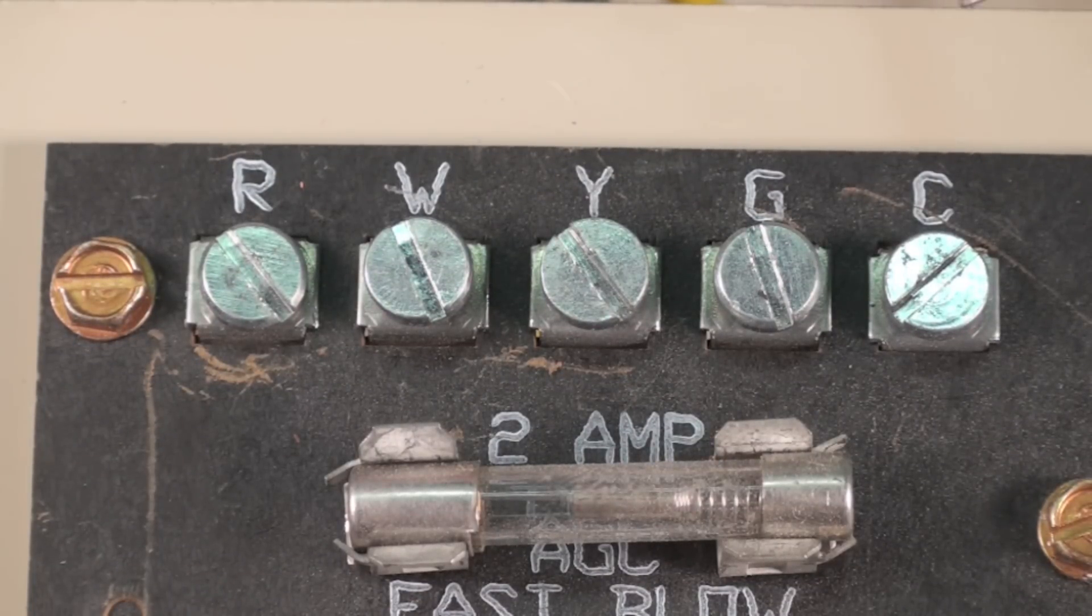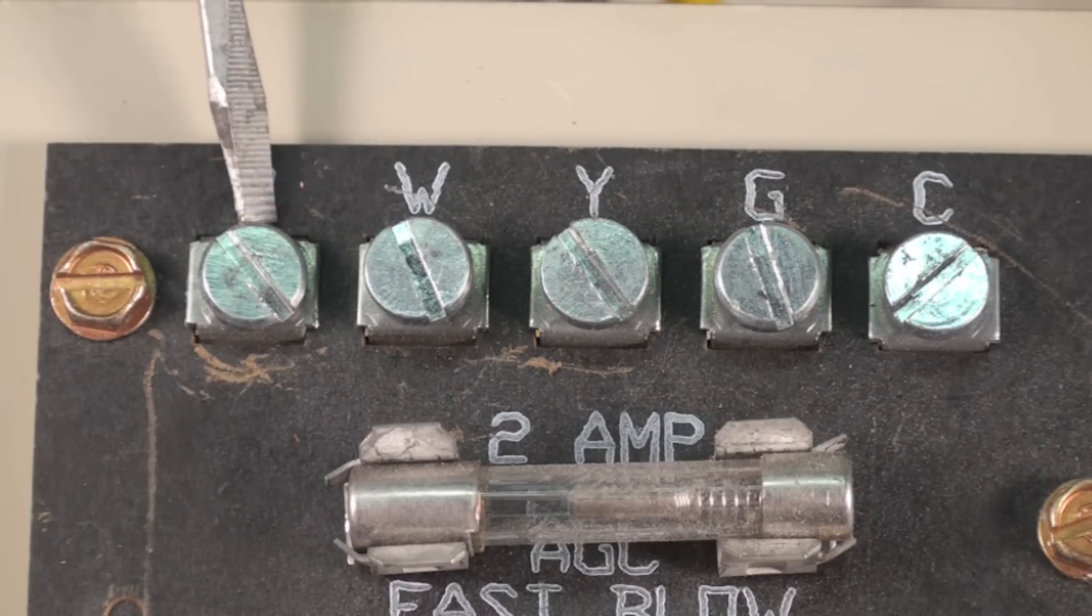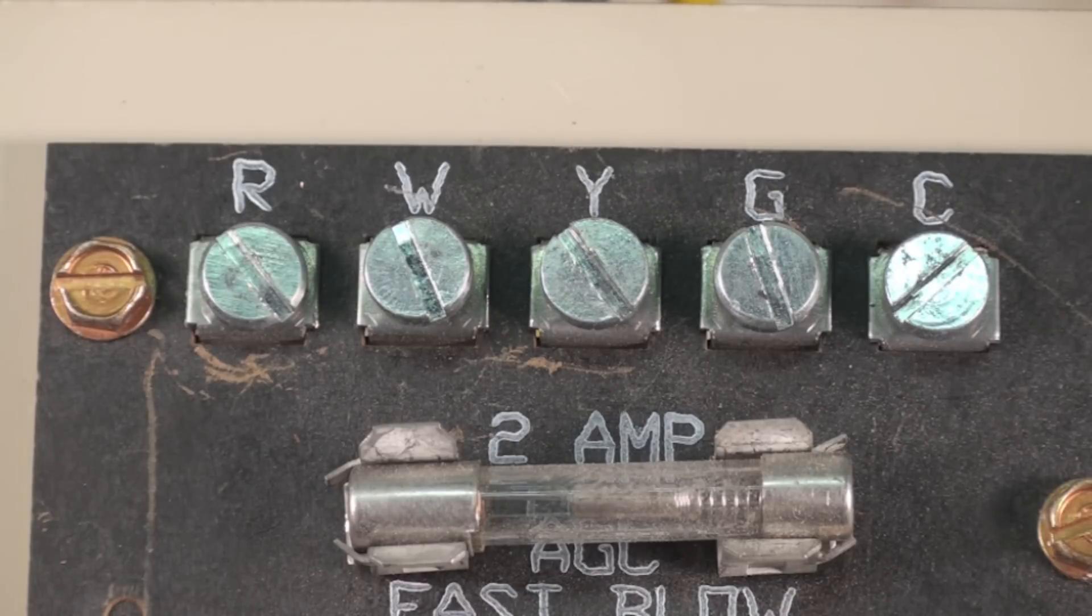I'd start out with C and R. That's low voltage power. If I want to know if there's power to this, 24 volts, I would go from R to C. That would tell me that the 24 volt power source is working.